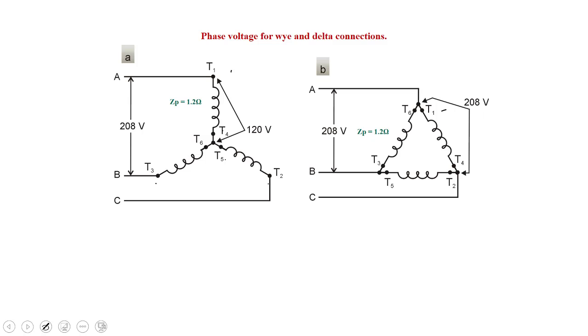All right. Well, what's the difference here? If you recall back in theory, when I connect the load up in Y, and I take the same supply and I reconnect it into delta, we're going to see 3 times more current. So it's advantageous that if I start in Y, I'm going to get 1/3 of the current on startup as I would if I were to start it in delta. So we can use this to our advantage.